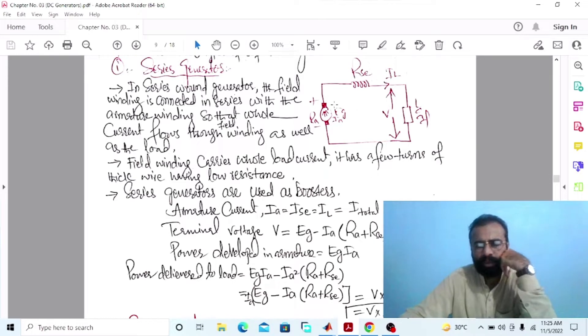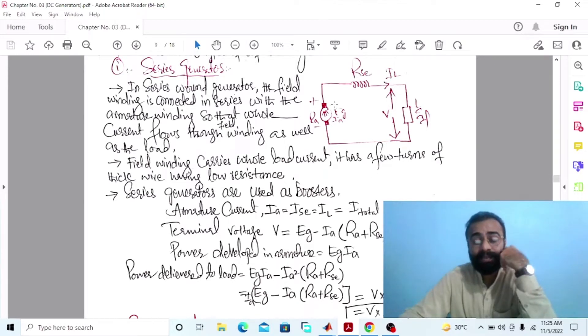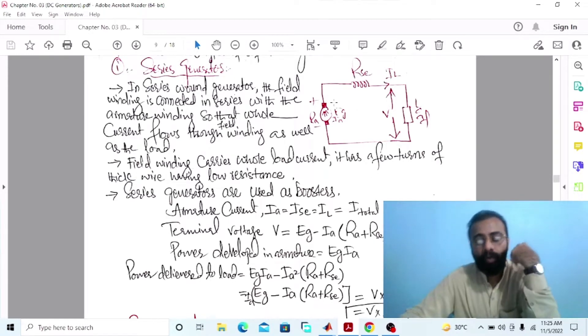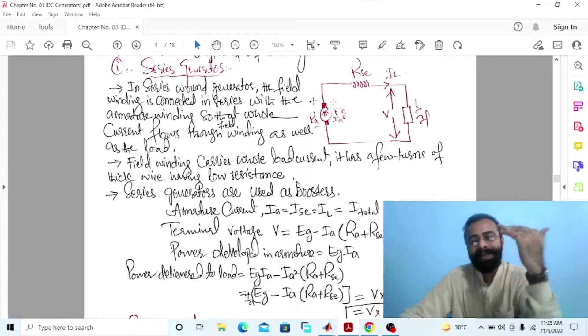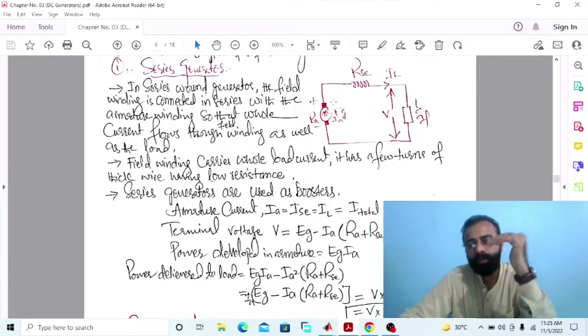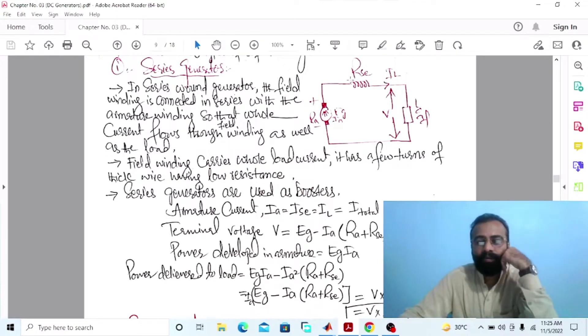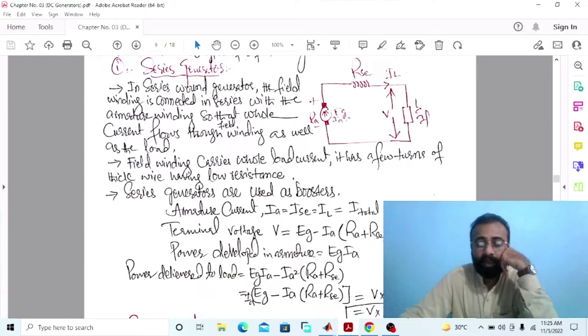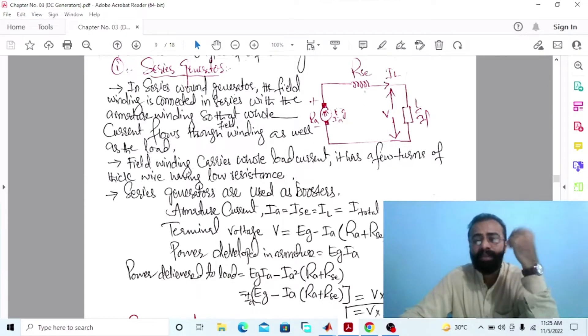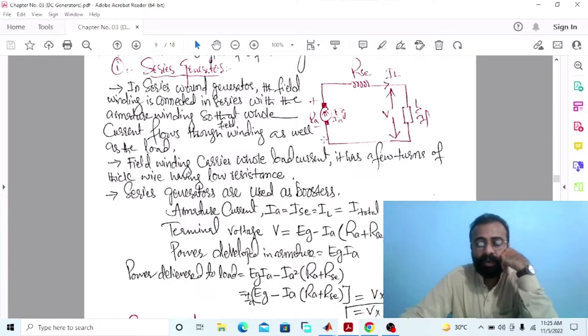The field winding has fewer turns of thicker wire having low resistance. According to the law of resistance, resistance is directly proportional to the length of the conductor and inversely proportional to the cross-sectional area of the conductor. If the cross-sectional area of the conductor is more, then it will carry more current. So the field winding carries the whole load current, and these series generators are used as boosters.